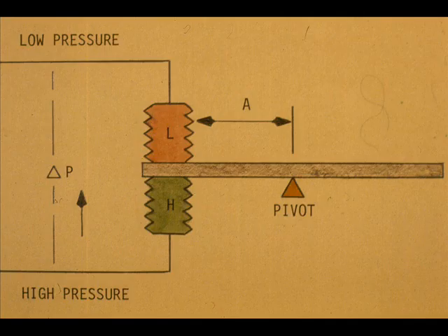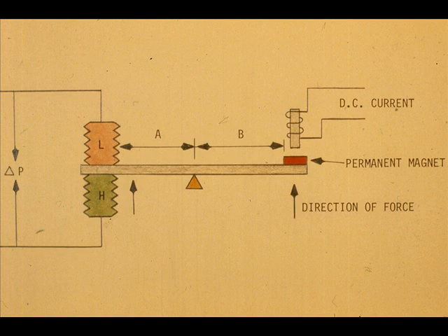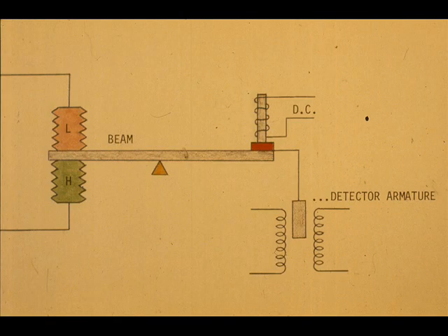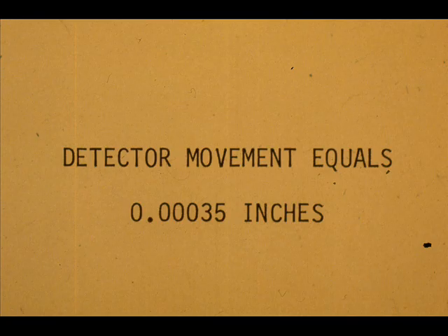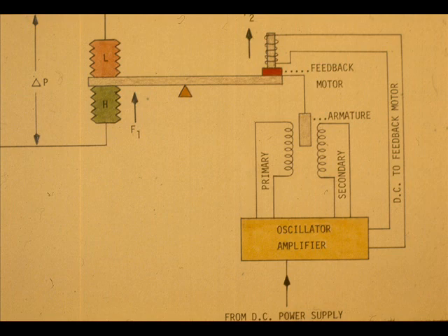In the force balance type transmitter, the force created by the differential pressure or pressure working through distance A is balanced by an electrical force working through distance B. A detector armature seeks a relatively fixed position to maintain beam balance. The total armature movement for full span of the transmitter is three or four ten-thousandths of an inch. An increase in differential pressure changes the armature position and increases the transformer's secondary voltage input to the oscillator amplifier. The increased DC output causes the force motor to rebalance the beam and bring the armature back to the original position.